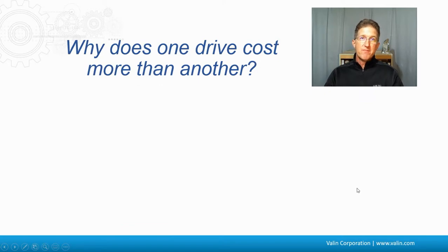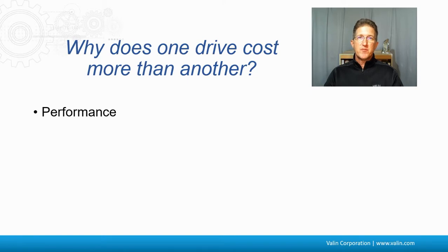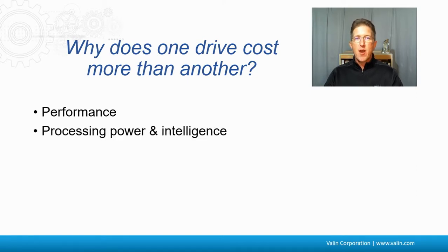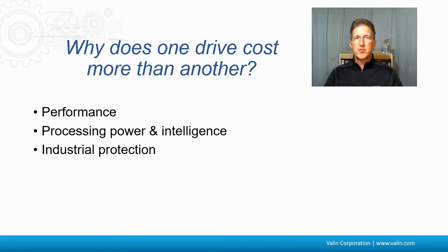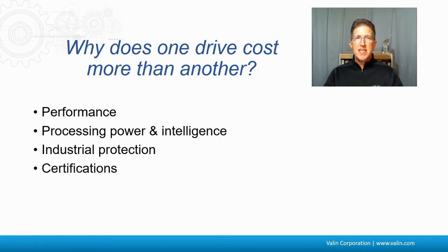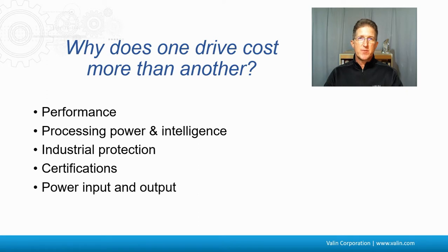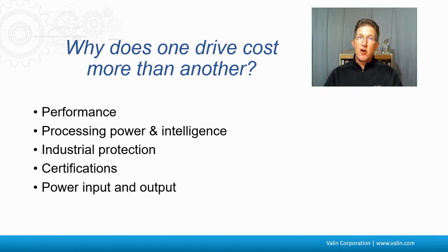Why does one drive cost more than another? There's performance — some drives have more processing power, more intelligence, faster processing, and more industrial protection from mains filtering, I/O protection, vibration, or temperature protection. They may carry certifications like CE and UL. Then there's power input and output: a drive that takes in 120V AC is more expensive than one that takes in 24V DC because it needs an internal power supply. A drive that handles 460V or outputs 20 amps is more expensive than one outputting 2 amps. The power supply, capacitors — it all factors into cost.